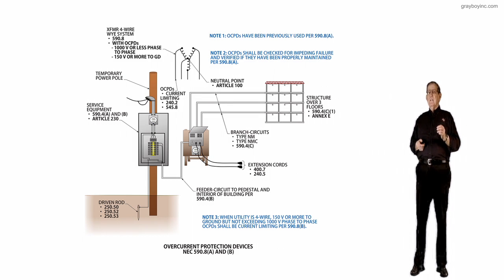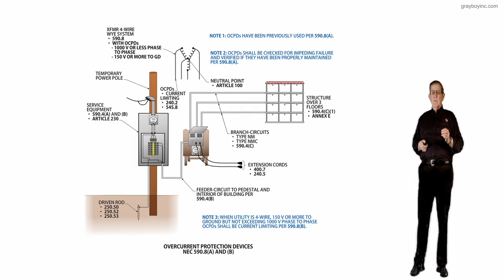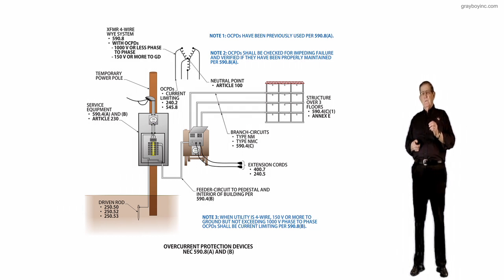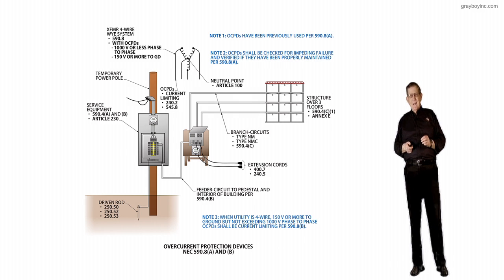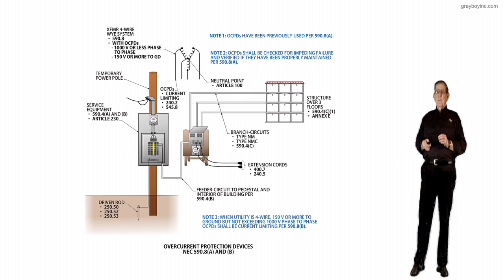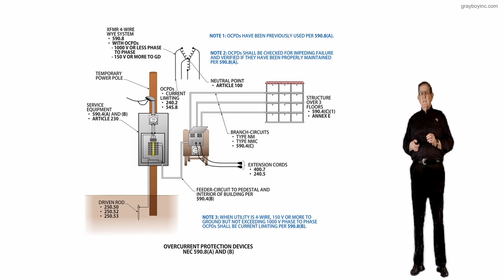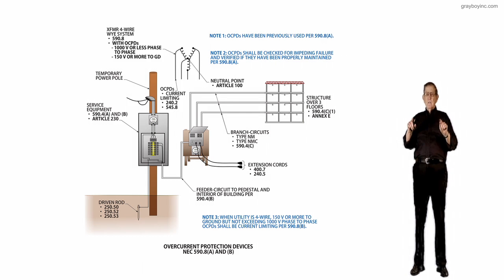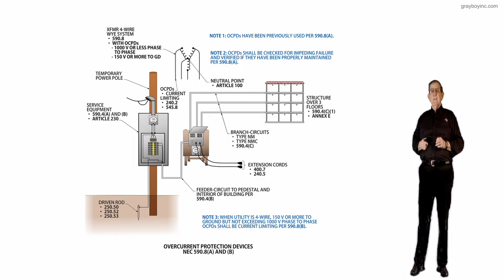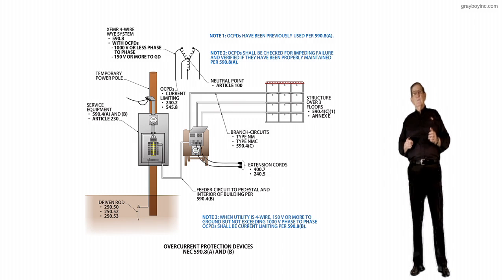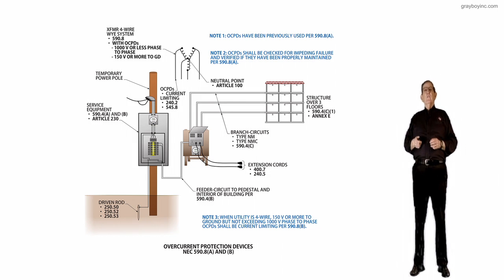Solidly grounded wye electrical services of more than 150 volts to ground, but not exceeding 1,000 volts phase to phase, shall be current limiting. Now notice this is only, the way I read it, on your 277/480. Now to review this, first let's take a look at the callout at the very top of the illustration at the left side.